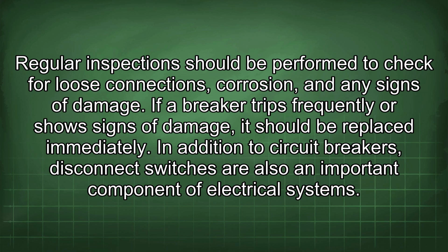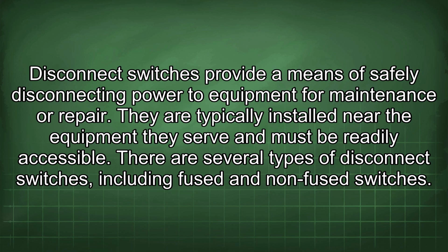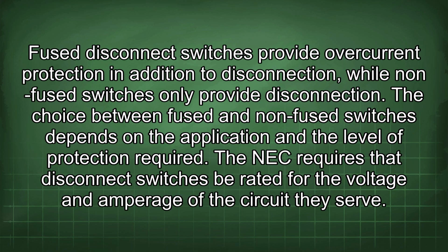In addition to circuit breakers, disconnect switches are also an important component of electrical systems. Disconnect switches provide a means of safely disconnecting power to equipment for maintenance or repair. They are typically installed near the equipment they serve and must be readily accessible. There are several types of disconnect switches, including fused and non-fused switches. Fused disconnect switches provide overcurrent protection in addition to disconnection, while non-fused switches only provide disconnection. The choice between fused and non-fused switches depends on the application and the level of protection required.